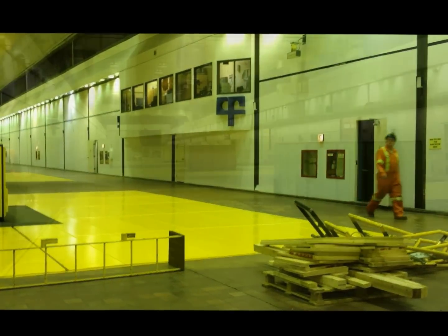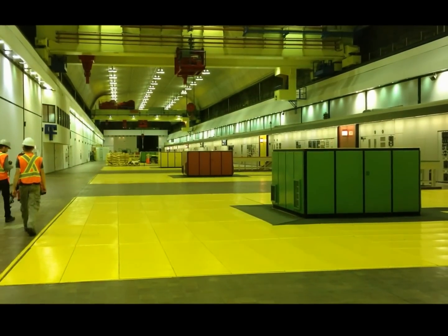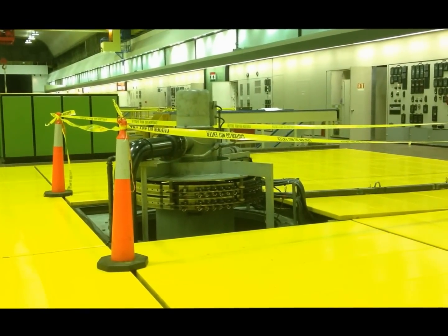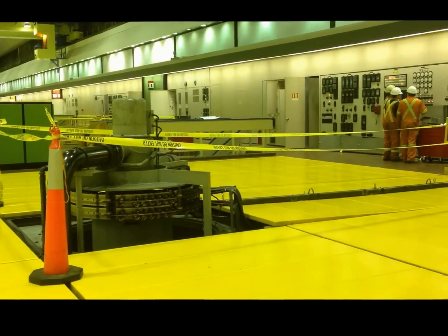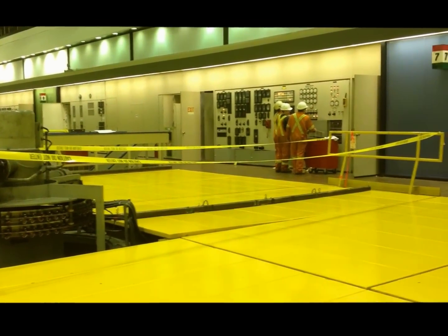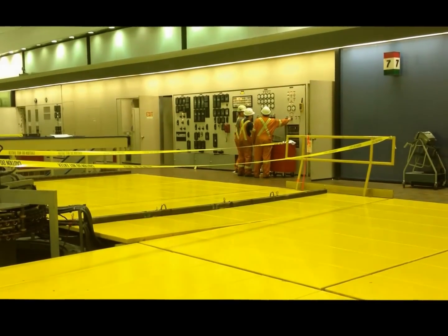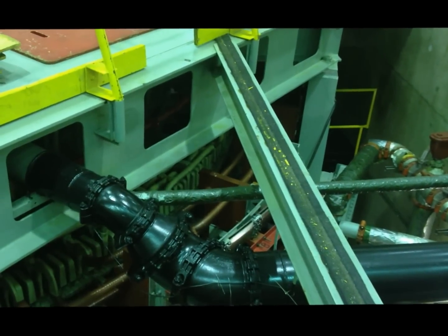It's a bit of a dance, really. What we have to do is get people to move out the old transformer — you remove your oil, move the transformer out of the powerhouse, which is a pretty tight space. In fact, the powerhouse is designed to fit the transformer. So basically you take the first transformer out and replace it with new, then connect all of the wiring and the protection equipment, and fill it with oil.